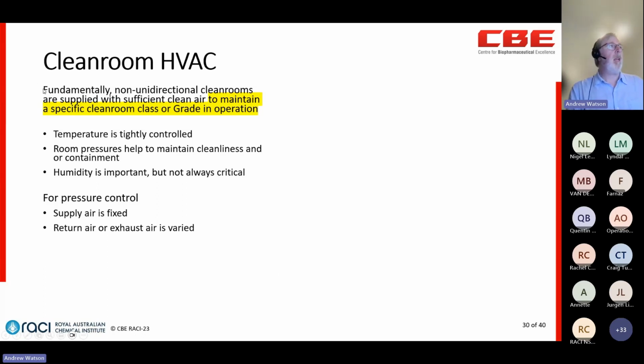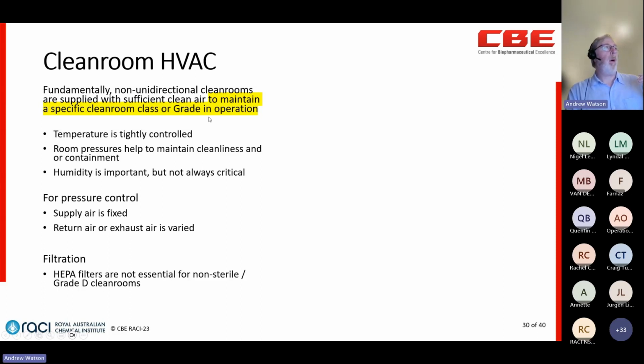A fundamental thing to remember is that for non-unidirectional clean rooms, you provide sufficient air to maintain a specific clean room class or grade in operation. There's a whole lot of other rules of thumb people get tied up in, like air change rates or the number of airlocks to get into a particular clean room. Fundamentally, that's what you're trying to achieve.